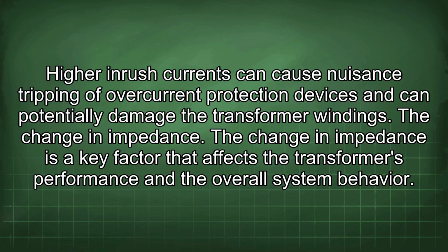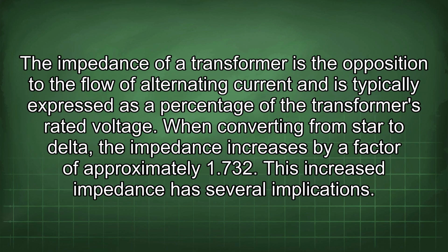The change in impedance. The change in impedance is a key factor that affects the transformer's performance and the overall system behavior. The impedance of a transformer is the opposition to the flow of alternating current and is typically expressed as a percentage of the transformer's rated voltage. When converting from star to delta, the impedance increases by a factor of approximately 1.732. This increased impedance has several implications.